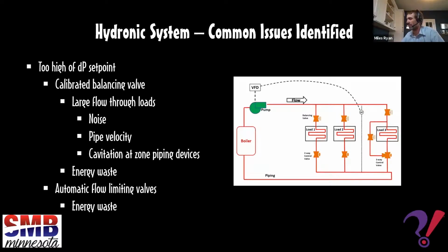And sure enough, when I got there, I found that the differential pressure set point that pump was controlling to was 30 pounds differential, which for the TAB professionals, you're probably thinking that seems a little high. Maybe the rest of you are not familiar with it. It might mean nothing to you, but I will tell you it's alarmingly high. You don't really see set points that high. But I called the TAB guy on the phone. He had been there the previous week, and I said, what's going on here? It's set to 30 pounds. Is that what you used?